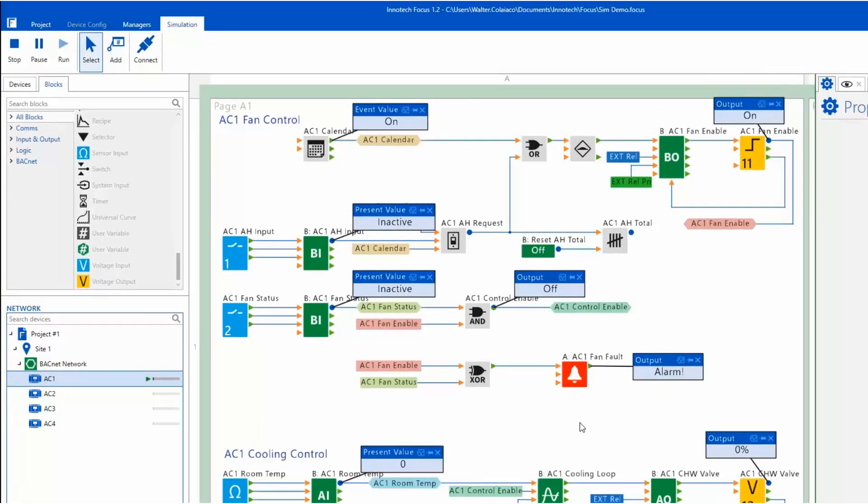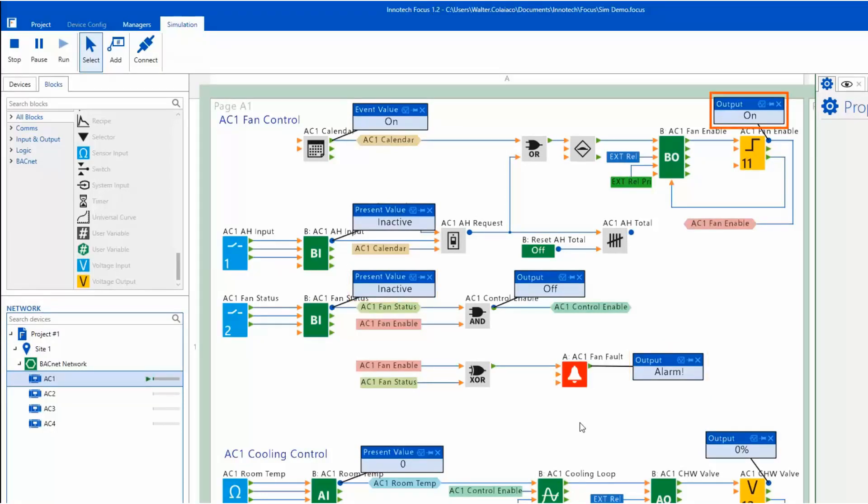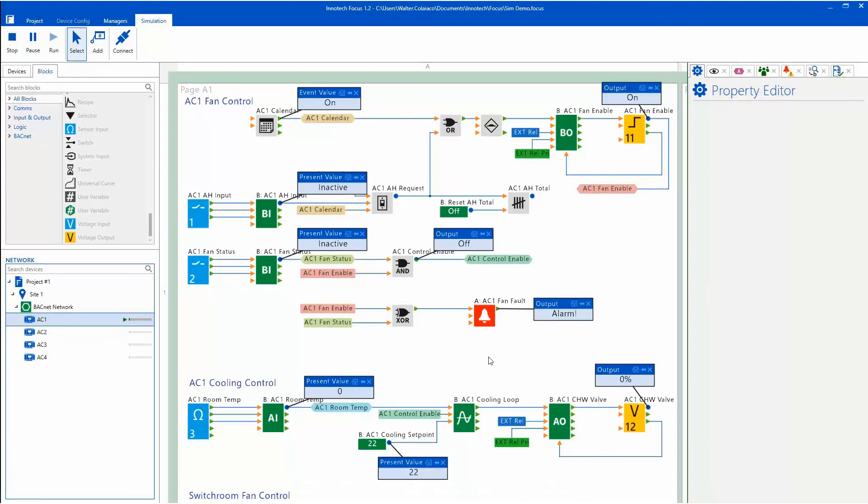In this example, the fan fault is active as the fan status is off and the control enable for the fan is on, essentially confirming this segment of the logic is working as intended.